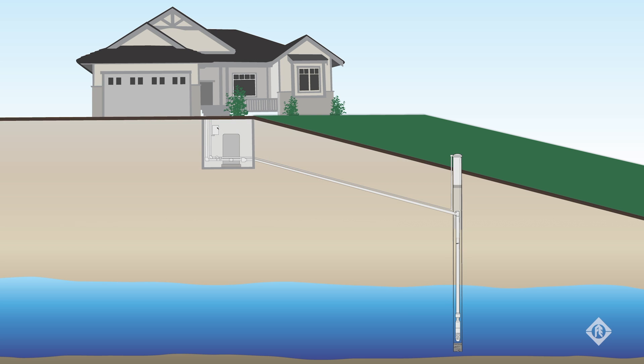The data we need to have is the following: one, static level and pumping level of the well at the required flow rate. You need to know how far you'll be lifting water out of the well tank or open body of water. This height is based on the distance from the surface of the water to the point of use. In a well, the water level will change as we draw water from the well, so depending on the well's capability to supply water, that change in level can be dramatic.